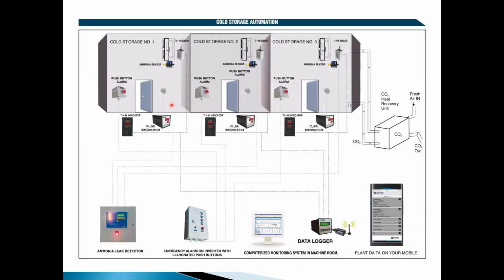Typically, if you have a potato cold storage or a positive temperature cold storage, you can have temperature and humidity sensing, because you want to maintain higher humidity and higher temperature so that you do not lose moisture from the product, it does not shrink, and you do not lose the weight of the product. Then we need to maintain the evaporators. We have the wall station, so we need to check that there is no ammonia leakage. We may have to monitor the temperature and humidity inside the room. We have to monitor the CO2 level and operate our exhaust fans or other systems to maintain it.